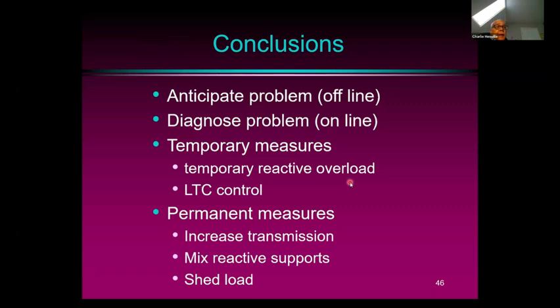So what we can conclude from that then is that the system planners, we want them to anticipate the problem offline. So they want to plan for whatever contingencies they can think of and determine what control actions might be taken. In the extreme case, of course, shedding load. They can diagnose the problem online by measuring the output at various locations and the voltages at various locations. They can allow temporary overload of various pieces of equipment, particularly generators and maybe shunt capacitors, but shunt capacitors very little. You can try and control load tap changes to see if the load can be controlled a bit, but there's not a lot of scope in that.